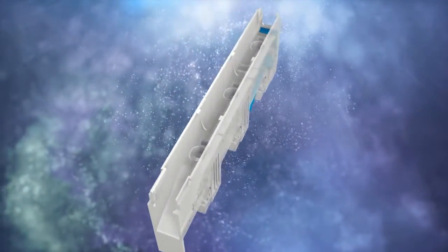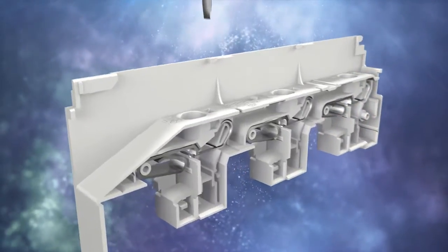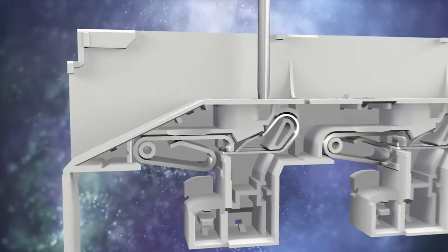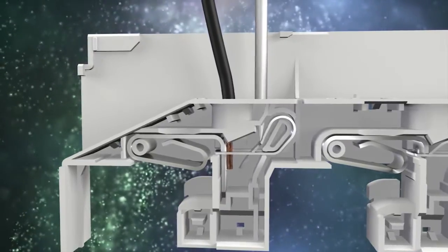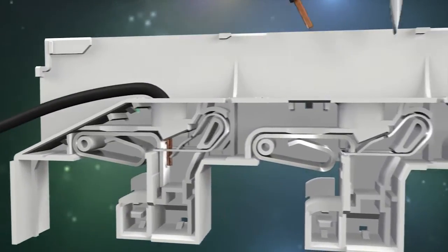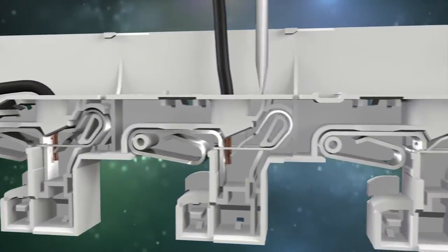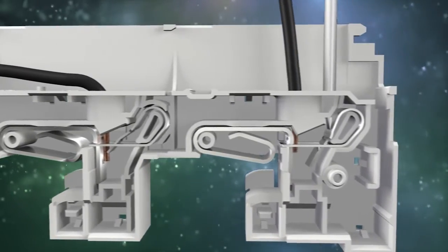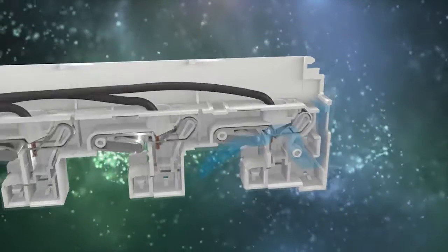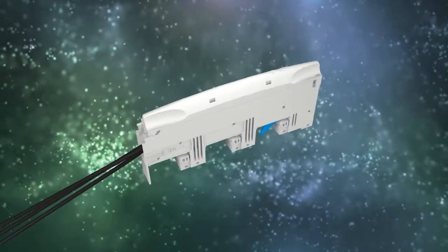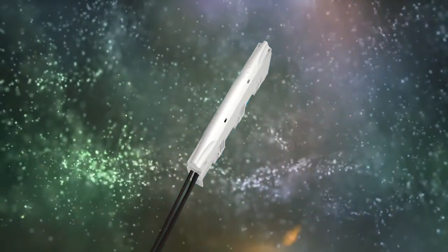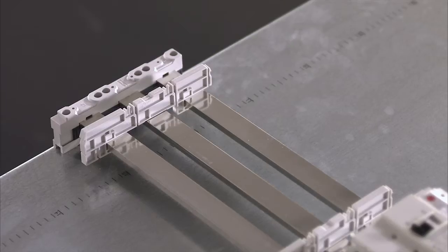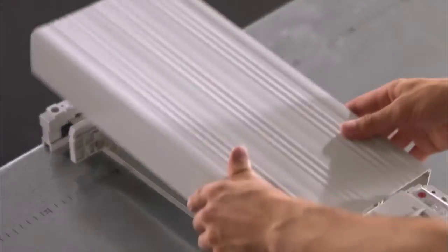The Creto connection module offers an especially compact connection technology. Just 20 millimeters wide, it enables quick and easy connection of three round conductors ranging in size from 1.5 to 16 square millimeters using spring-loaded terminals. Unused areas of the bus bar system can be fitted with single or multi-pole covers.